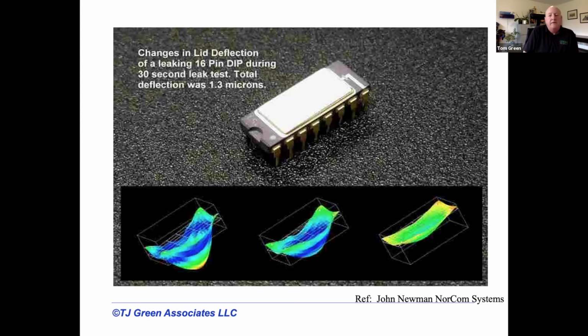So you can relate that deflection to a change in pressure. The chamber itself is 100% helium, or you could test in air, but you deflect the part and then look at the rate of relaxation, if there is any. From that you can calculate a leak rate.